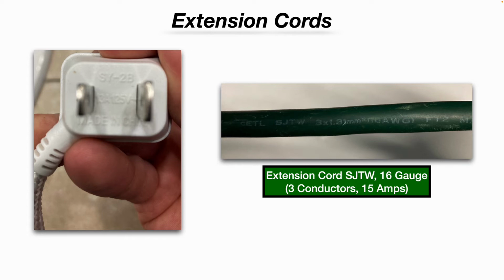We can see on the side of the cord, it is an SJTW 16 gauge. So inside the conductors are 16 gauge wire and has a 15 amp max capacity. And you can look that up online, do a Google search. You can say, what is the ampacity of a 16 gauge wire? Find out for yourself. My point here is somewhere on your extension cords, there should be some sort of rating. If there's not a rating, then on the cord itself, you should be able to identify what kind of cord it is, what the wire gauge is, and then do a Google search to tell you how many amps that extension cord is capable of handling safely. And you never want to exceed the max ampacity.